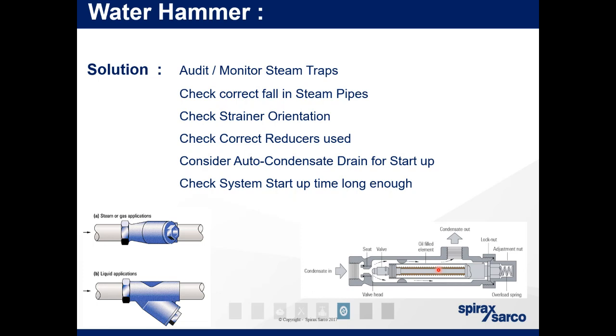Yeah, so effectively any system or any allowance of wet steam in your system will produce condensate in your steam pipe, and that will then carry over into a water hammer or can cause water hammer. So if you have insulation that's broken down, so it's cooling your steam system, it's creating condensate on the inside of the pipe, that eventually, if it's not drained properly, will cause water hammer. Trap failures, where they've failed closed, will introduce condensate into your steam system by effectively building up.